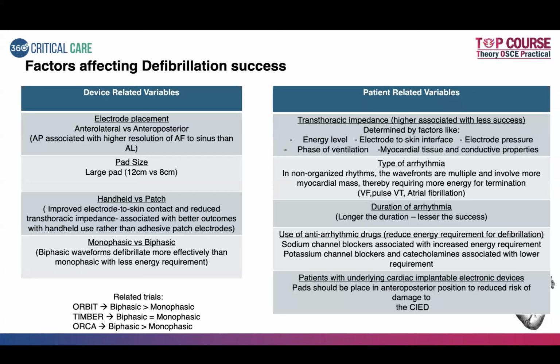So factors affecting defibrillation success, you can split into device related and patient related. Under device related, you need to assess the electrode placement, the pad size, the handheld versus patch, and monophasic versus biphasic. Electrode placement, they've seen that anterolateral is not as good as antero-posterior. In regard to the pad size, the larger the pad size, the better the distribution of current and better the effect. Handheld versus patch, with handheld, there is improved electrode to skin contact, so better the shock delivered and better the response. With monophasic and biphasic, biphasic is supposed to be superior to monophasic.